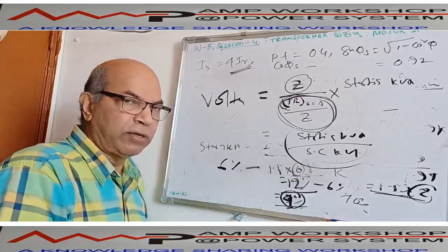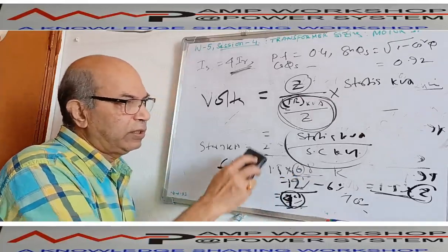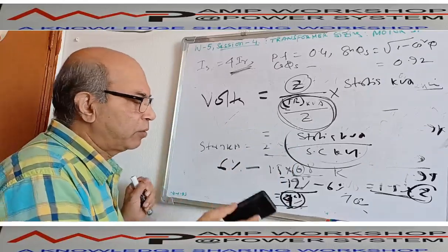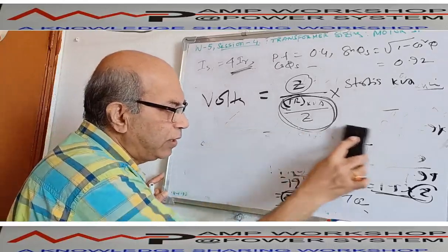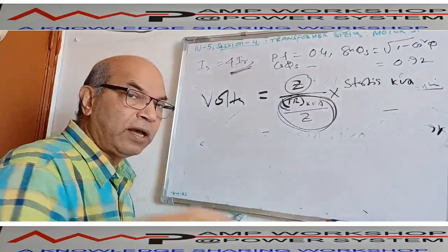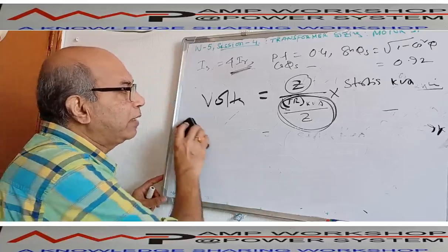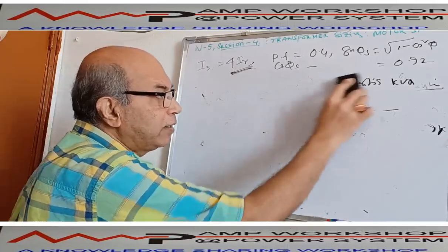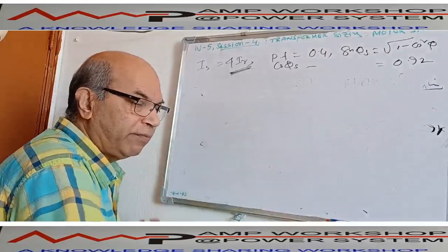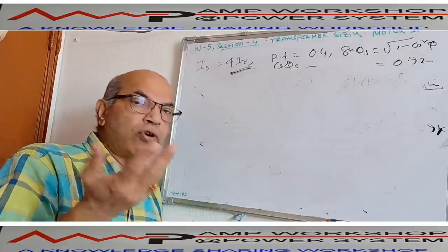From this calculation, we can say even if the transformer is designed for 10% impedance, then also this starting voltage drop is possible. But one of the points we have said is that this additional voltage drop we have considered based on the rated condition. So at the full load condition, how do we maintain the transformer terminal voltage? We do it by the off circuit tap changer. We define transformer voltage in terms of no load condition.